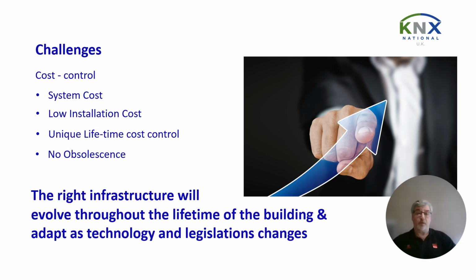Another cost consideration should be obsolescence. Consider the lifetime of a building. Why put a closed proprietary system in that could be obsolete in 5 or 10 years, depending on that manufacturer's whim or even solvency? It's a cost that is hardly ever factored into cost models. The KNX Open Protocol standard and large pool of manufacturers ensures that obsolescence is a thing of the past, greatly reducing the lifetime cost implications. And as we have seen previously, closed proprietary systems can be very costly to update if requirements change, and may require a new parallel system to be installed. The KNX Open Protocol standard means that upgrading a system is simple and very cost effective, as usually no significant alterations to the bus infrastructure are required.